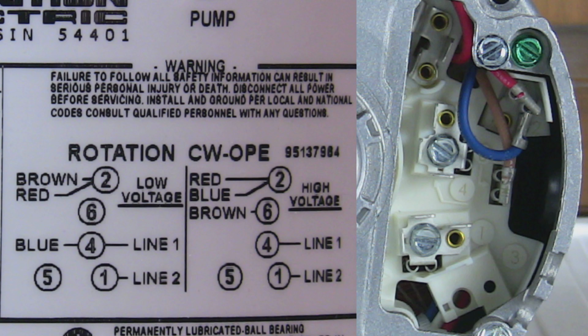Number 5. Return to the 3 wires coming from the machine. Locate the green wire and connect it to the ground symbol. The ground symbol is an isolated terminal connected directly to the motor's chassis. Of the 3 machine wires, always connect this wire first. If it is not present, then a new wire must be installed.